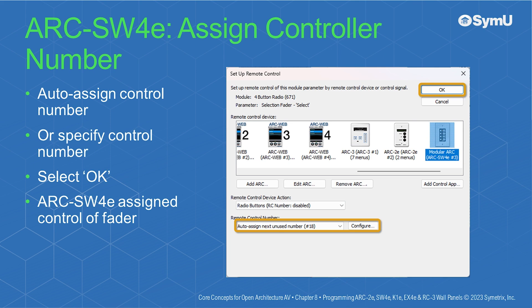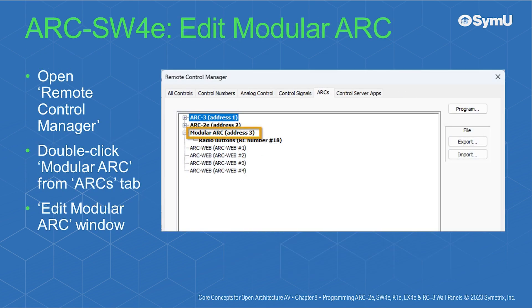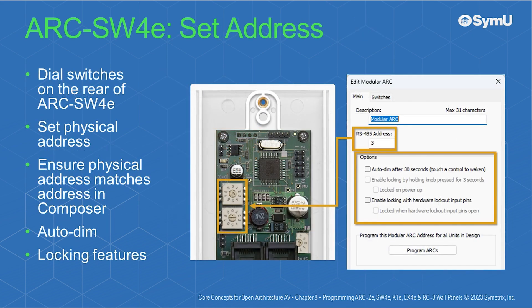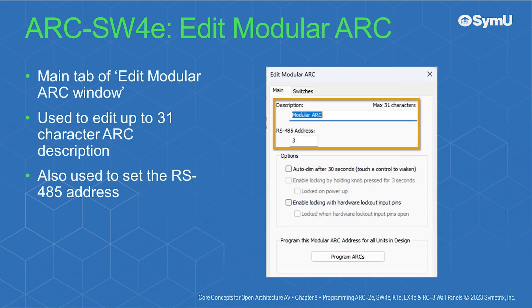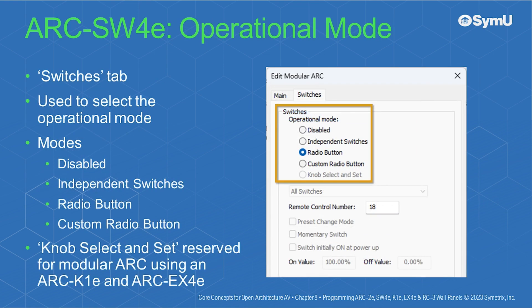The Arc SW4E has now been assigned control of the fader. Open Remote Control Manager and double-click Modular Arc from the Arc's tab to open the Edit Modular Arc window. Use the dial switches on the rear of the Arc SW4E to set the physical address, ensuring it matches the address in Composer. Auto-dim and locking features are also enabled from the main tab. The main tab is used to edit up to 31 characters of the Arc description and set the RS-485 address. The Switches tab is used to select the operational mode of the Arc SW4E.